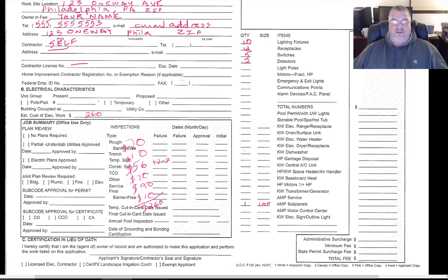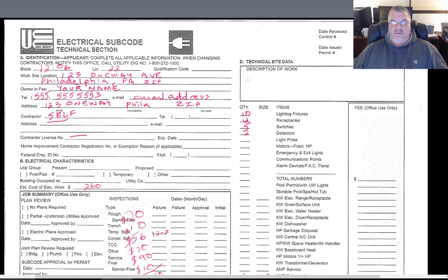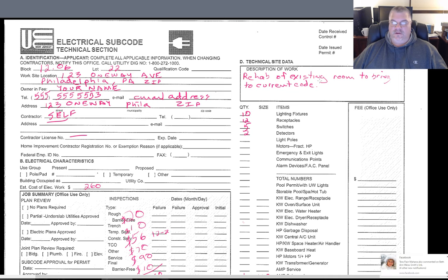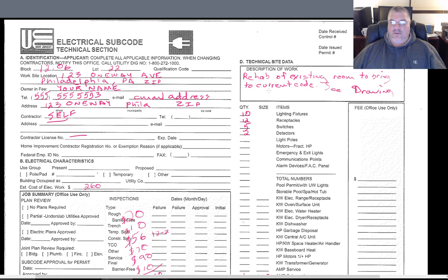You also need to describe your work. This is a rehab of the room brought to current code. The code for a room is the 6/12 rule: there can be no more than six feet between an outlet and a corner, and no more than 12 feet between outlets on any one wall. So if you have a 30-foot wall you'll probably need three outlets. The application says 'see drawing,' so let's save this document and create that drawing.